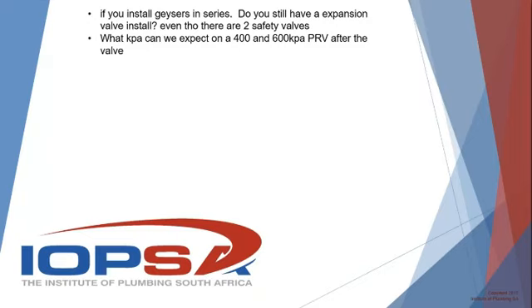Yeah, I think what he's asking is whether a safety valve can be used to fulfill the role of an expansion valve. As Patrick said, there are two scenarios where the TP valve opens up: one is temperature, yes, but the other is pressure. But the opening pressure of a safety valve is 150%, as you say, plus or minus 10%.